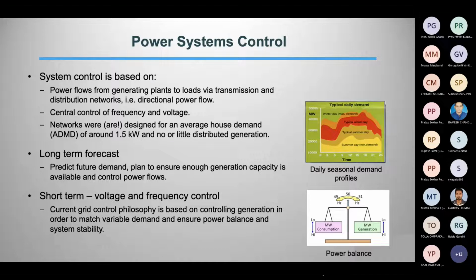Networks have been designed over the years based on experience: house demand increases or decreases during the day and night, but when some houses switch on loads, others might not. So they use what's called after diversity maximum demand (ADMD) at the main distribution transformer—measuring the demand of all houses connected to it and dividing by the number of houses gives an average demand of about 1.5 kilowatt.